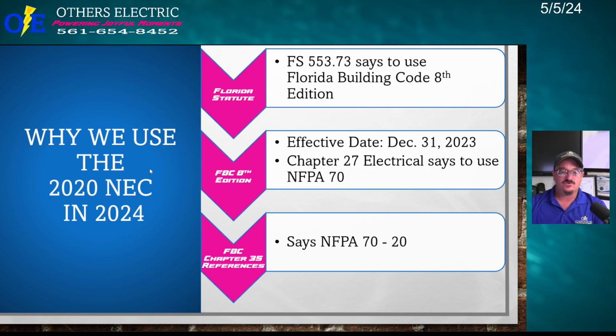So why do we use the 2020 NEC in Florida in 2024? So Florida Statute 553.73 says to use the Florida Building Code 8th edition. Okay, and if you read that, it tells you to use the Florida Building Code 8th edition, which is effective December 31st, 2023. So basically, January 1st of 2024, in Florida, you are required to use the 8th edition of the Florida Building Code.